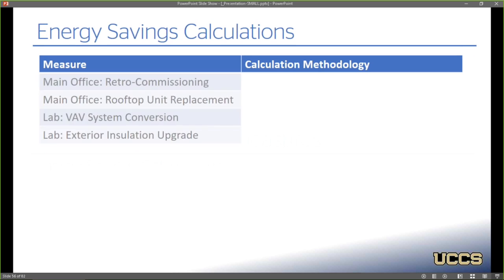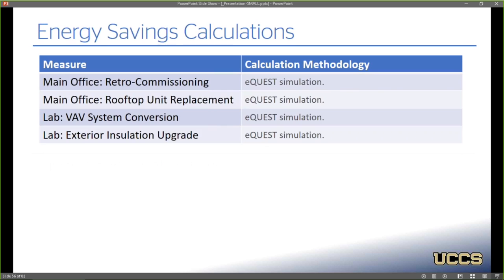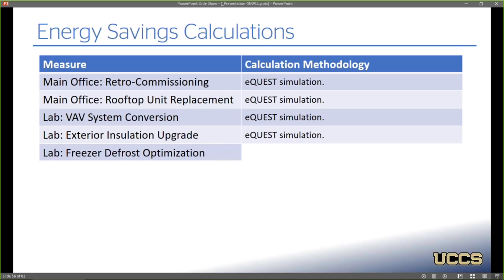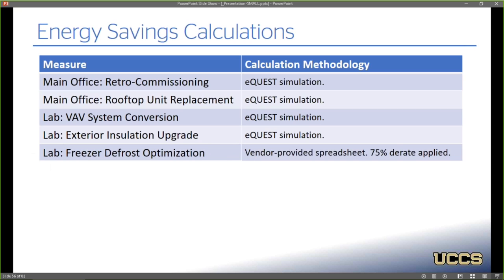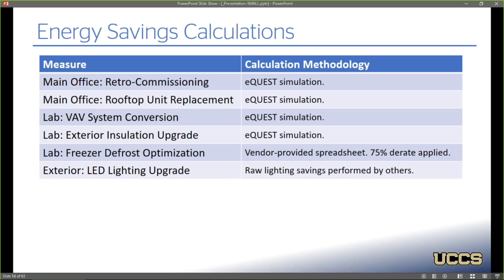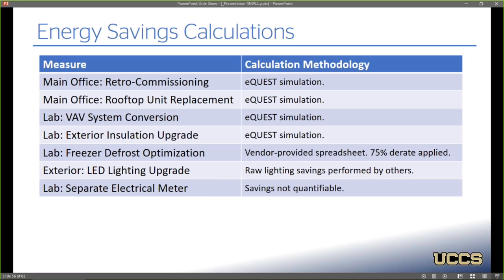So for the energy savings calculations, the primary methodology here was an eQuest simulation, and that was for the Office RCX, the major mechanical measures, and the lab exterior insulation upgrade. The lab freezer defrost optimization was done with a vendor-provided spreadsheet with a 75% derate. The LED lighting upgrade was done by others, but I did do some incentive analysis on that, which is why I'm including that measure here. And the separate electrical meter, those savings aren't quantifiable necessarily, so I didn't do any savings with that.